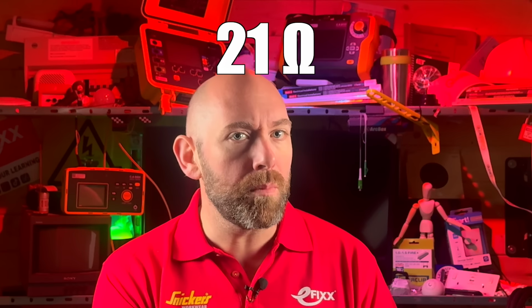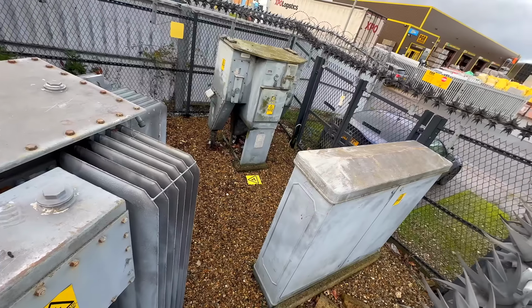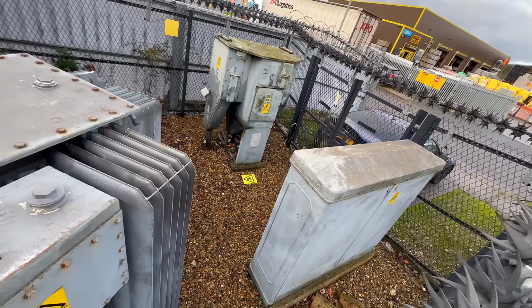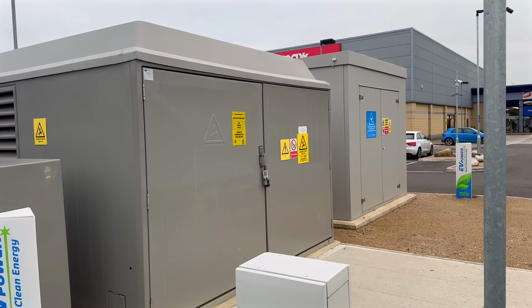There is one number that you may often hear mentioned on TT systems, and that's 21 ohms. So what is it, and is that the maximum permitted ZE for a TT system? Well, no. That figure relates to the distributor's earth at the supply transformer. It is not a requirement of your installation. Now, I didn't know this because I thought 21 ohms was the maximum ZE for a TT.